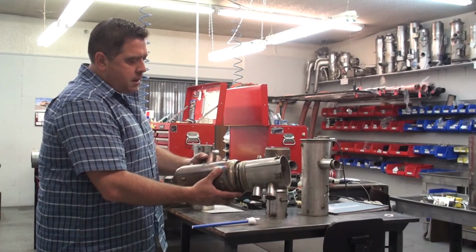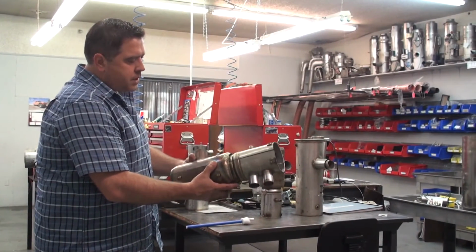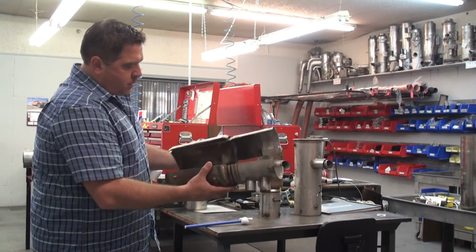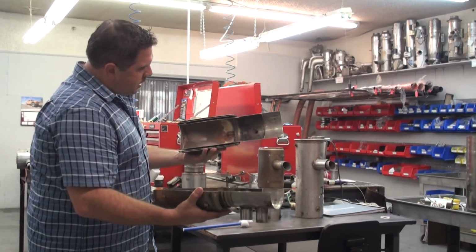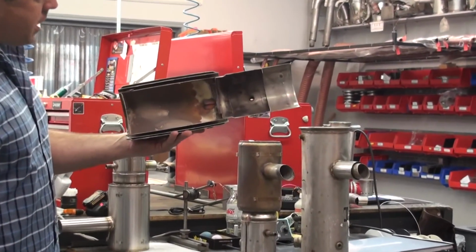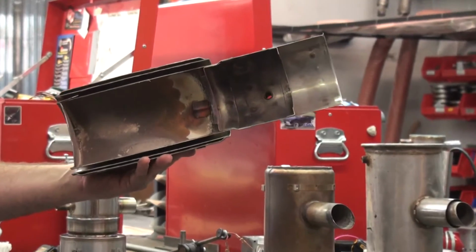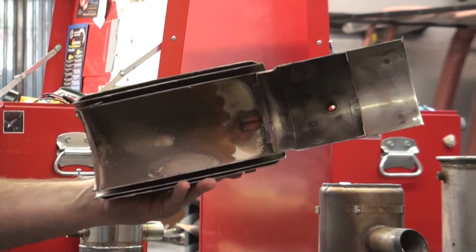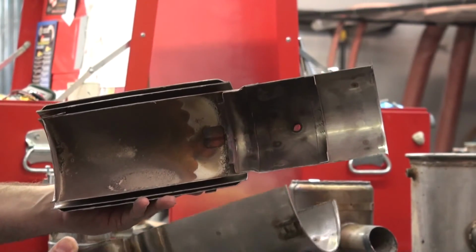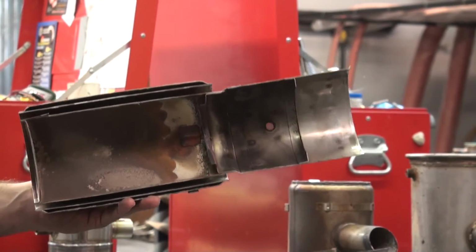So here we have a basic combustion tube for the Southwind heater, probably an 8259 that this came out of, that we've cross-sectioned. And in here you can kind of see what the burn does. Stainless steel is a great metal actually for combustion tubes. They will last if they're treated properly and the fuel pressure is proper and everything is working properly. They can make TBO no problem.